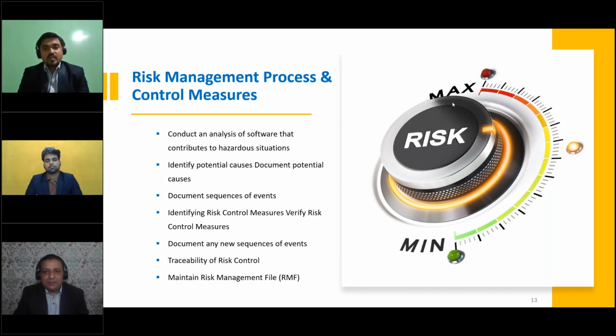According to this 14971:2019, they put a lot of scrutiny and a lot of emphasis on the residual risk. So nowadays you need to put your attention on the residual risk. First you need to mitigate your risk, and then look at the overall residual risk. Once you list down the overall risk, you then need to see the separate residual risk for your device. After that, you have to look at the production and post-production activities. You need to do the risk assessment for the production and post-production activities.